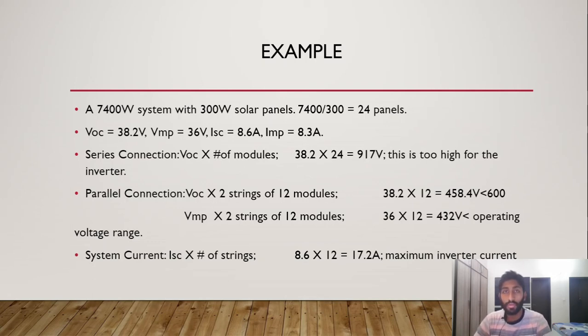You have to mix and match, go for an inverter that is not too oversized but a little bit above the solar system rated output power. So if you have a 5 kilowatt solar system, go for a 7 kilowatt inverter - that's going to be the best. Or you can go for a 10 kilowatt and then in the future you can add more solar panels if you have available space. Generally, don't go too high with sizing the inverter based on the solar system that you have.